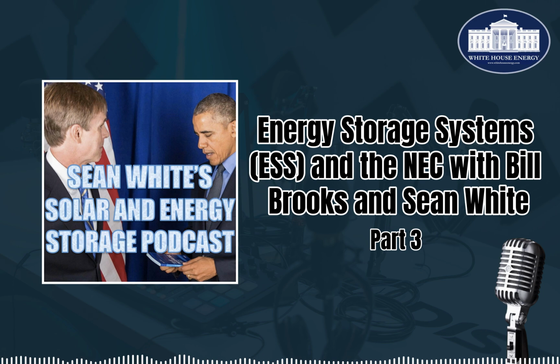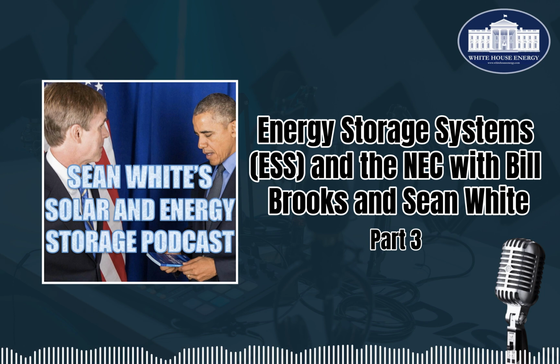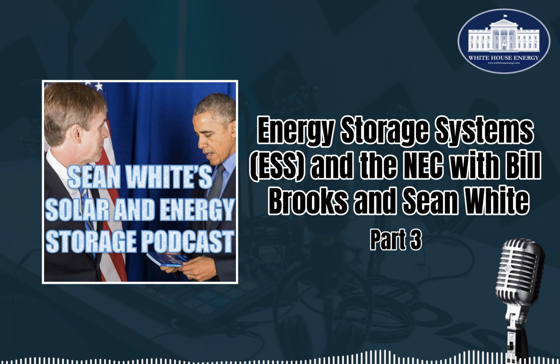So that has to do with the transformers they're using and stuff like that. In certain areas with commercial and industrial applications, certainly in Honolulu, you're going to have available fault currents that are well above 10,000 amps. And so the equipment is rated for that. Whatever the initial service equipment was selected based upon what the utility provided as their fault current calculation.